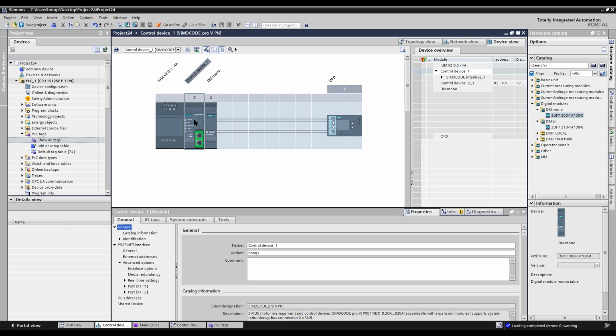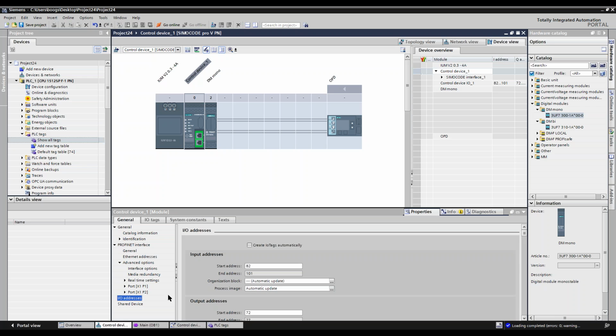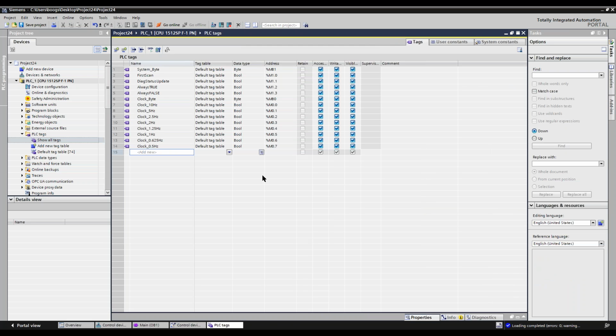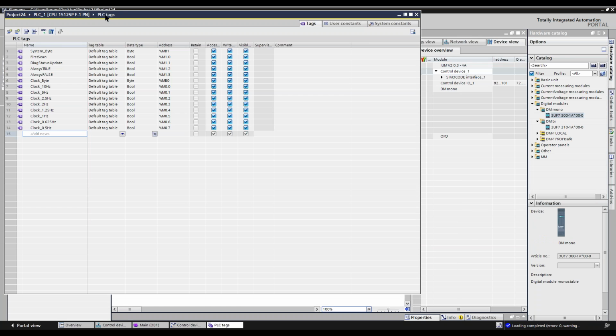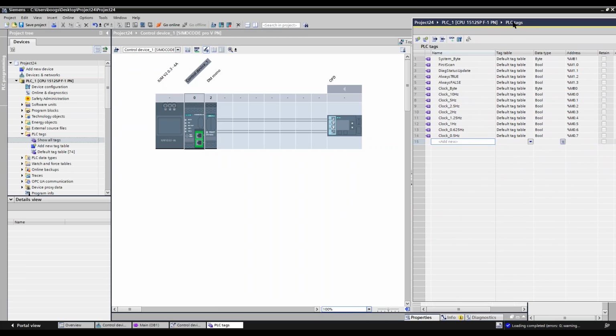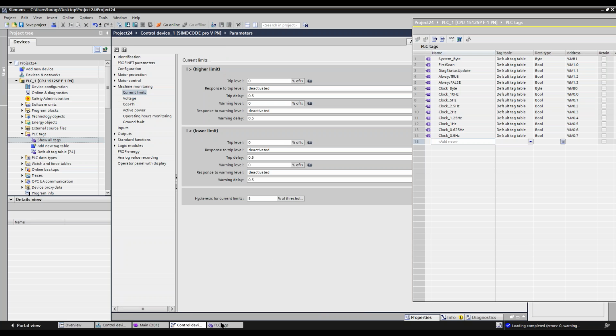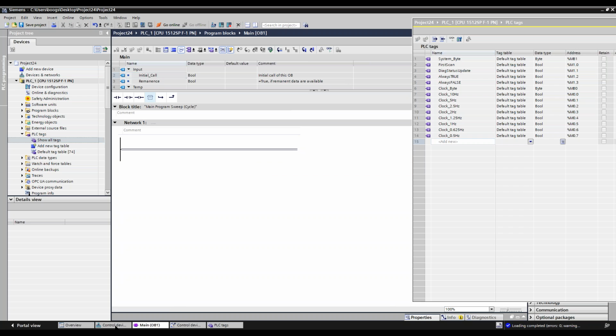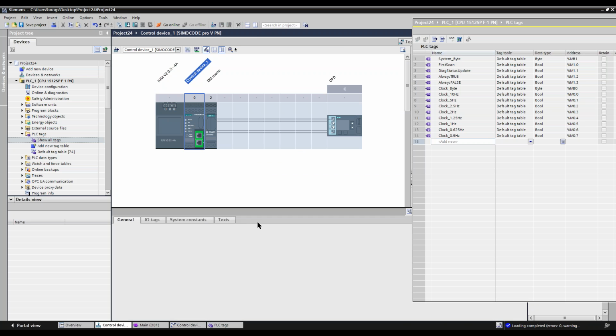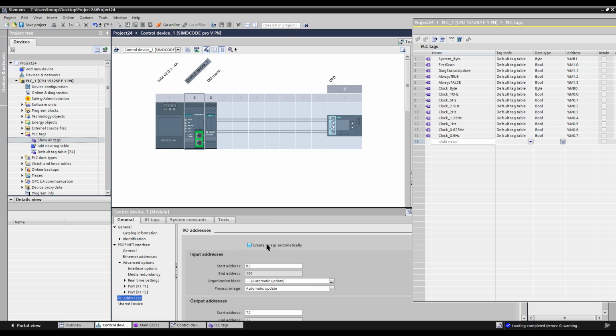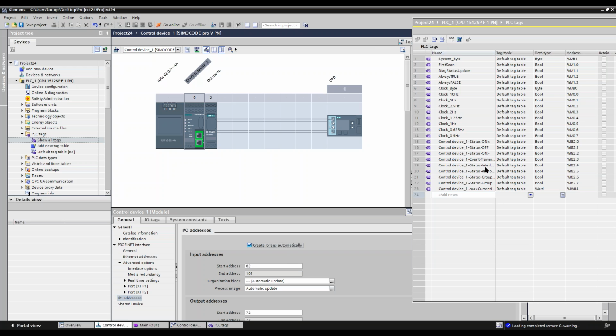I'm going to click here on the SIMOCODE, go to my Properties, General tab, and then come down here to I/O addresses. So that you know I don't have anything up my sleeve, I'm going to detach my PLC tag table and set it right over here. I'm going to go back to my SIMOCODE. And at I/O addressing, I'm going to say create I/O tags automatically. So I'm going to hit create, and look what it did automatically.